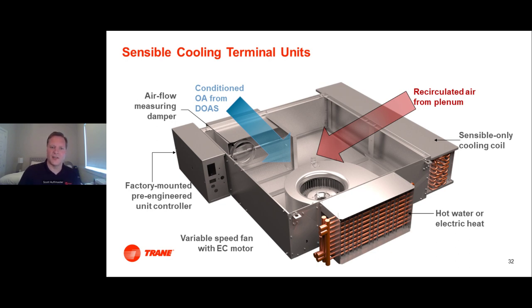So if you think of a chilled beam system, that's going to have recirculated air from the space. That air is going to get pulled through using a series fan through a sensible coil, and in this example showing a sensible only cooling coil, and it's going to supply that to the space consistently. We would have a filter upstream of that. We have the ability to get that as high as a MERV 13 filter if that's going to be what the space needs. This also has built into it essentially a cooling only VAV box, but what's going to control that is both occupancy and CO2 readings for the space. So we can optimize how much ventilation we're going to bring to the space based on that CO2 reading.